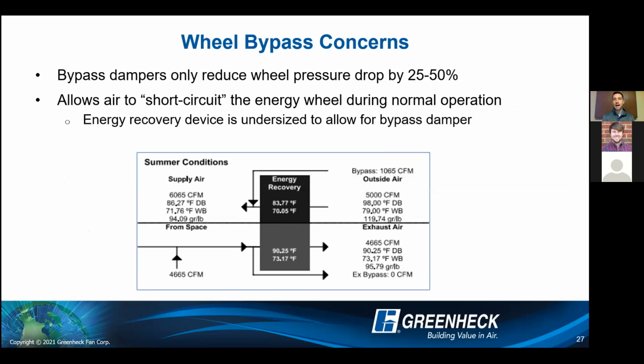One other concern not related to economizer is in certain manufacturers, what we see is bypass dampers do only reduce wheel pressure drop by 25 to 50%. But the big one is this allows air to short circuit the energy wheel during normal operation. And what I mean is they have to undersize the energy wheel so they don't have to expand their housing. And in order to move the overall supply airflow that they want, they actually have to bypass some outdoor air during normal operation because that specific energy wheel in this case is only sized for a maximum of 5,000 CFM.